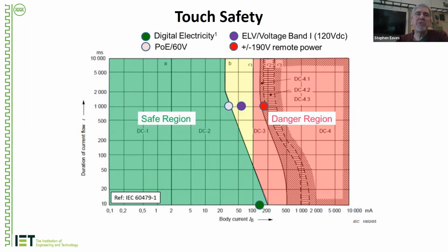So here I'm showing a couple of comparisons. I use some European measurements here. So you could look at the purple here in the yellow region. This is ELV, or band 1 voltage, as it would be described in the UK, which can extend to 120 volts DC. And to explain this chart a little bit, the lower axis is the body current that's formed. It extends from 0 to 10,000 milliamps on the bottom axis. And on the vertical axis is the duration of exposure. So in this little corner here in the lower left, that's a 10 millisecond exposure at 0.1 milliamps. So it's way in the safe region of DC1, which is all these regions here I'm pointing to. DC1, DC2, 3, and 4 are areas of exposure that have population numbers attached to them. So if you're exposed to those regions, you have higher and higher probability of cardiac fibrillation.